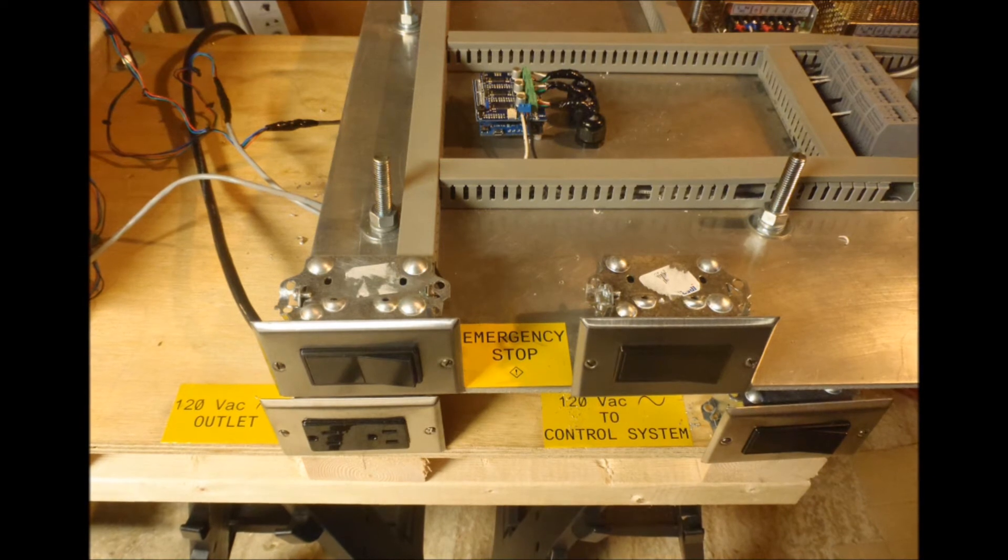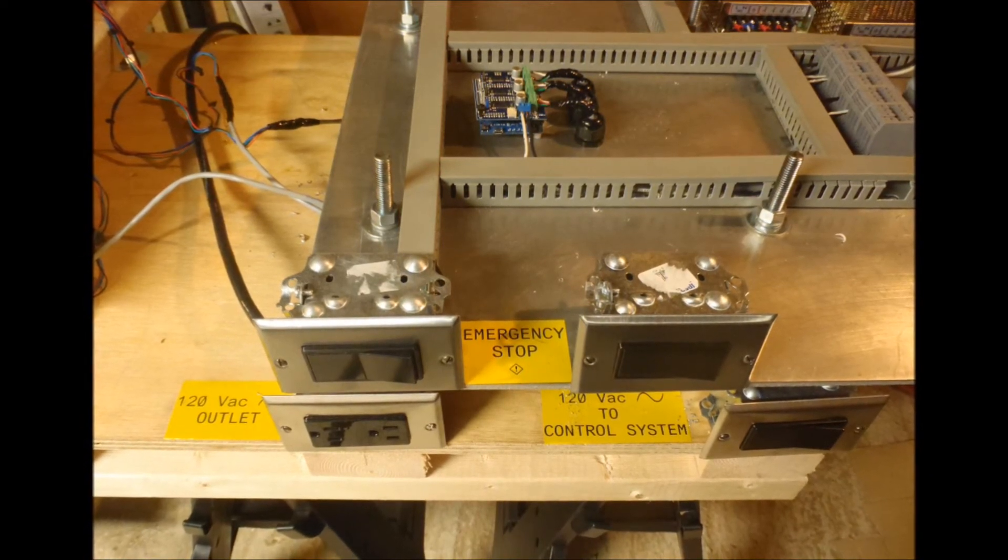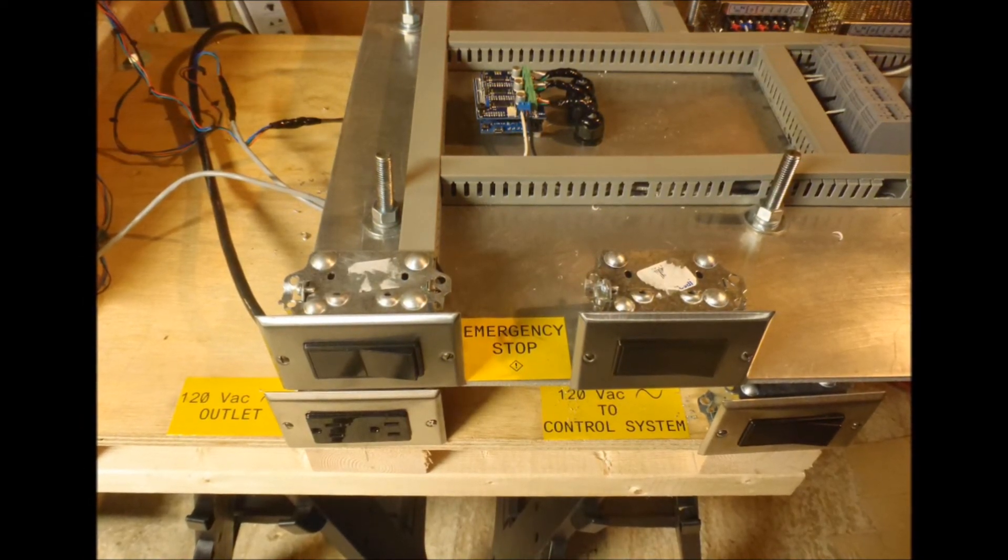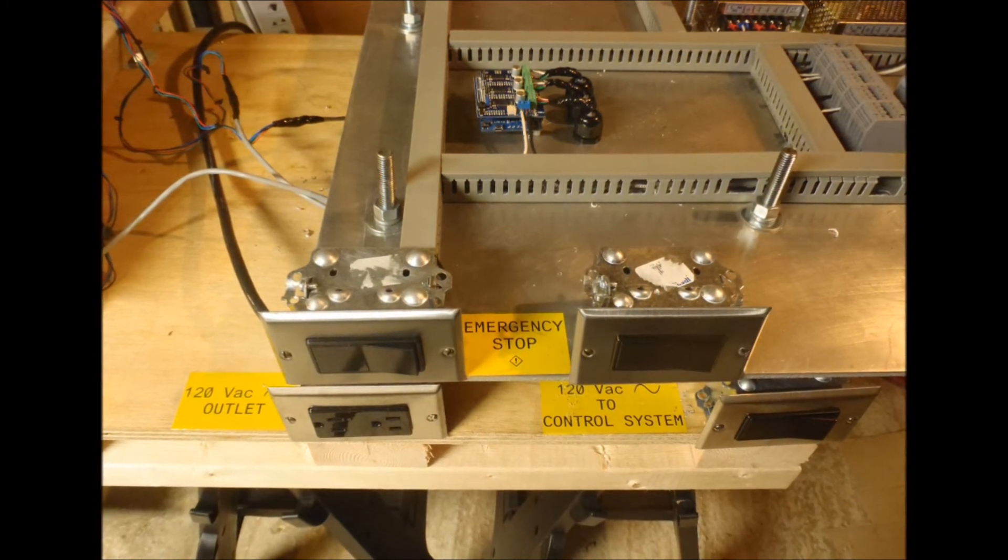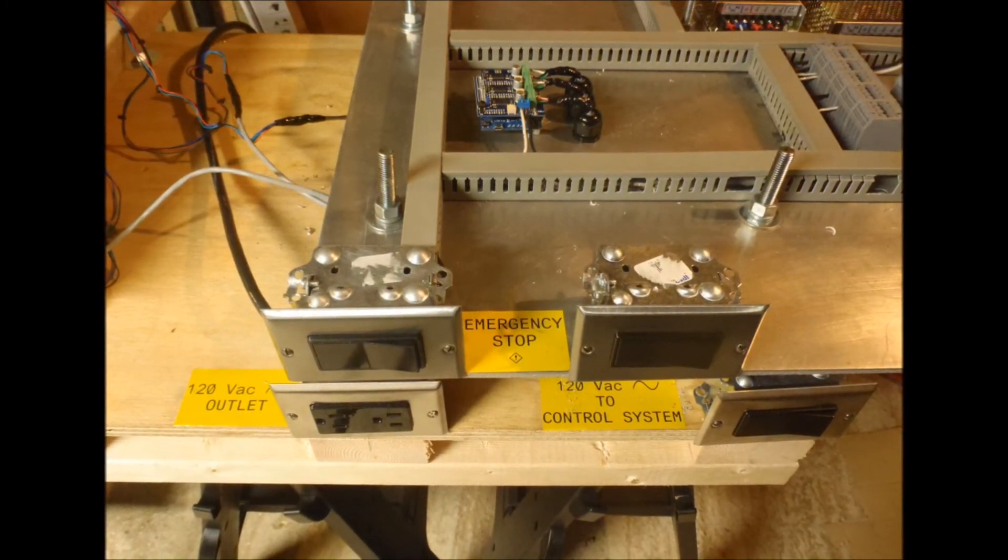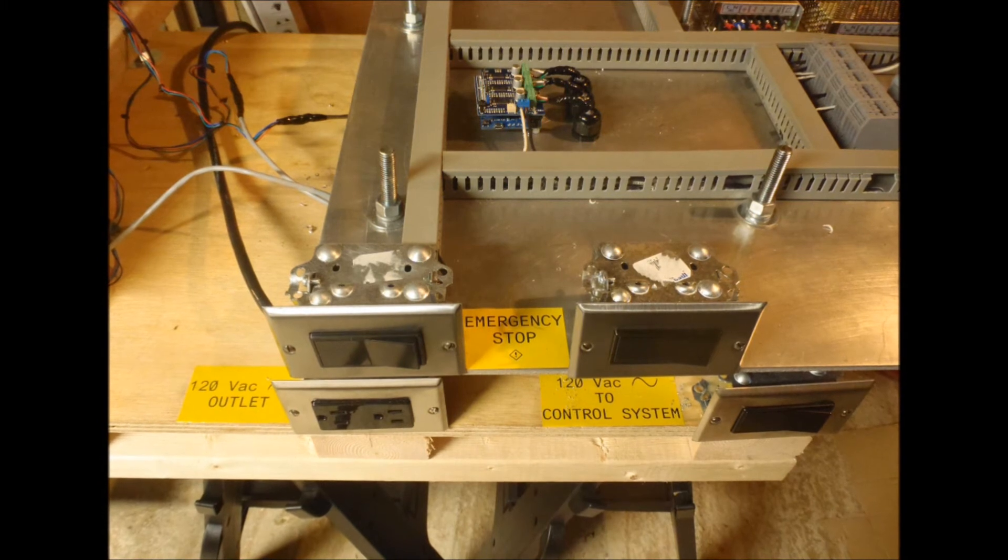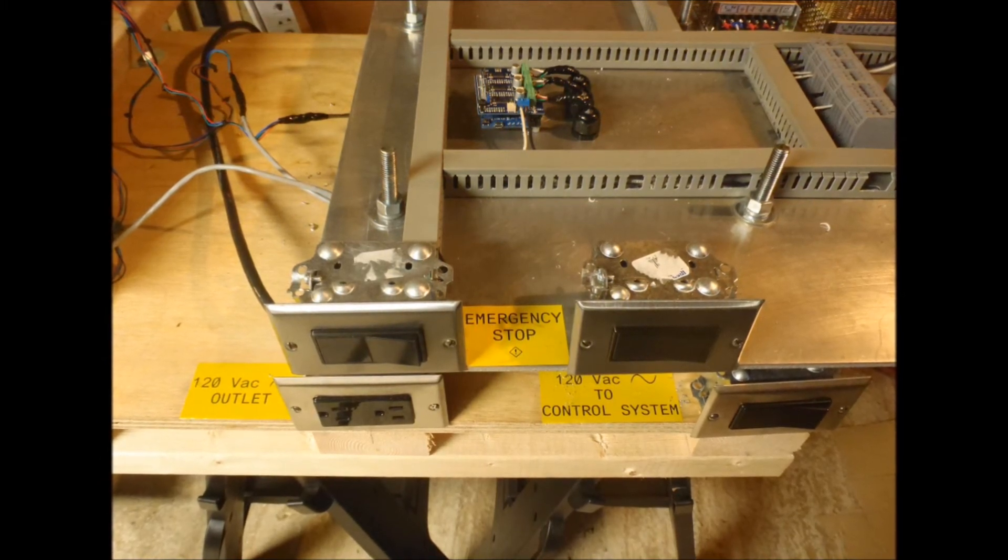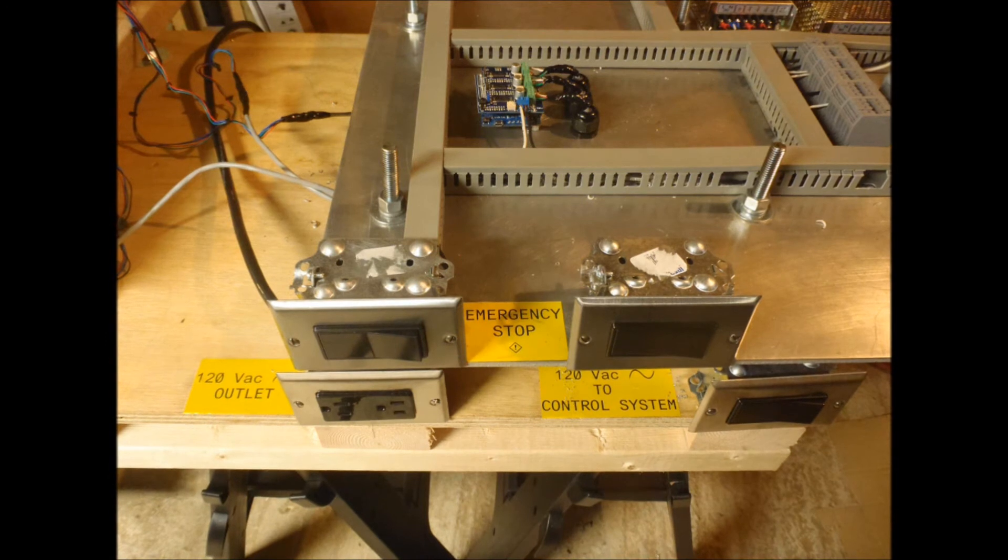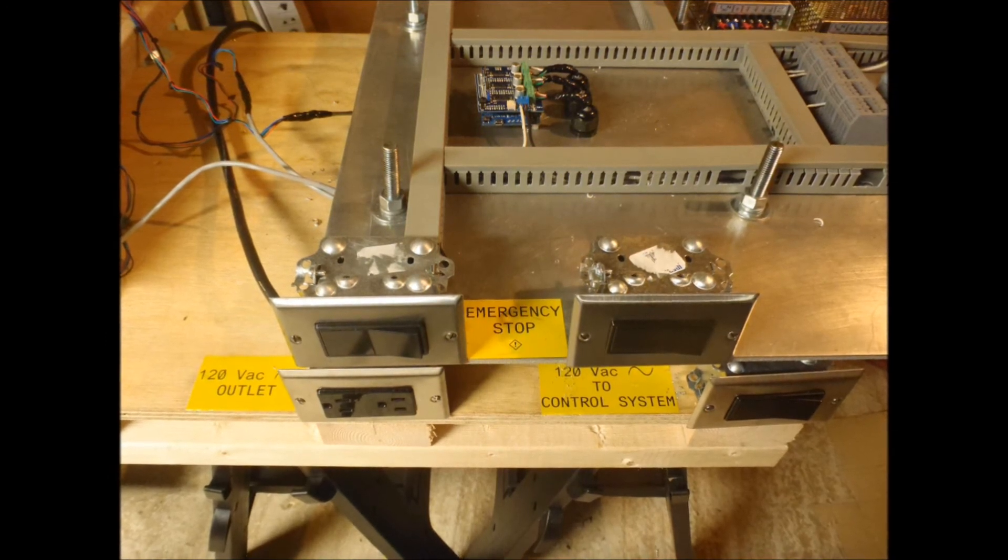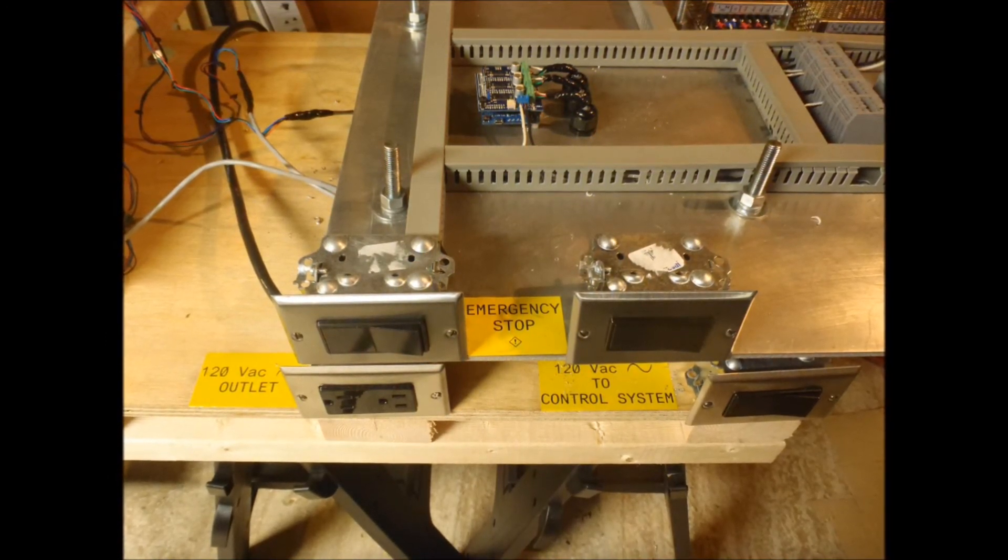We have another switch that will be wired for environmental controls to bypass the fan movement. Underneath that is the 120V AC to the control system, which cuts off all AC power to the DC power supplies. So ultimately that's your on-off button for the entire system.